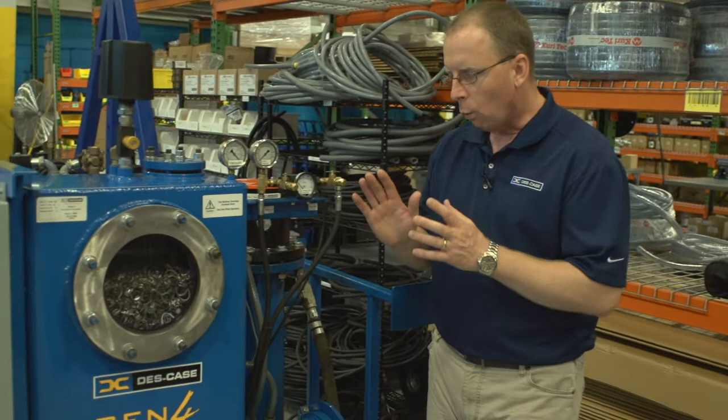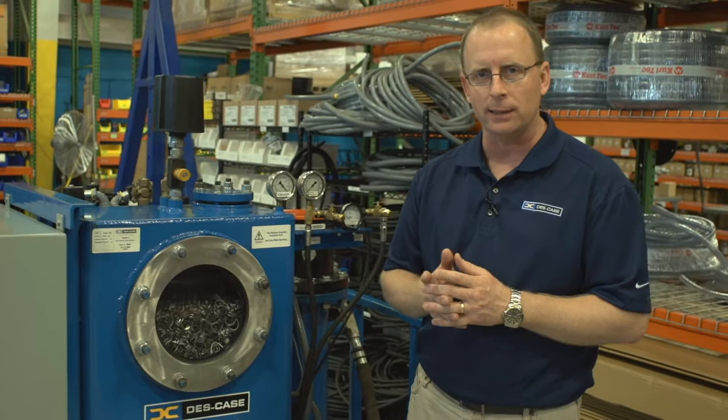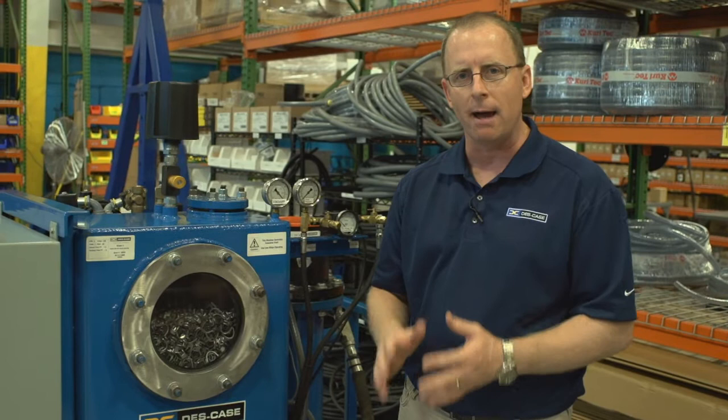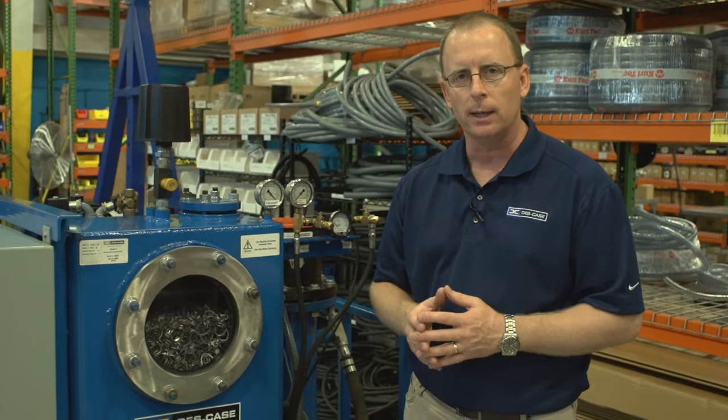One of the key features of the Des-Case HiVac system is the permanent dispersion media. The permanent dispersion media is a stainless steel saddle ring. These stainless steel saddle rings never need cleaning, never need service, never need replacing. These saddle rings are a 65 square feet per cubic foot media, meaning for every cubic foot of this media inside the tower there is 65 square feet of surface area.